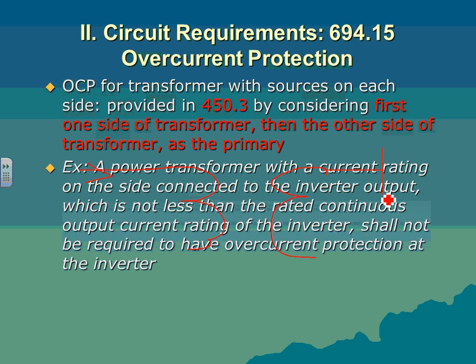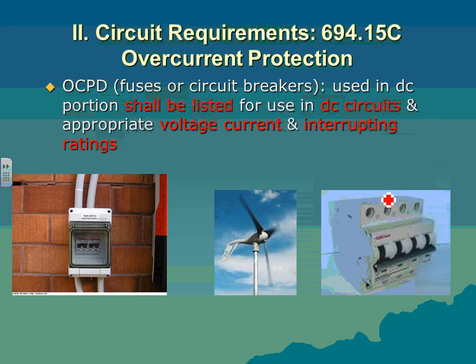And 450.3 will tell you 1.25 if there's no secondary here, and a bunch of other rules. And this talks about how an overcurrent protection device used in the DC portion shall be listed. The arc coming out of the DC circuit is bigger, so it has to be listed for DC. And again, you have to have the voltage and the current rating for that equipment.